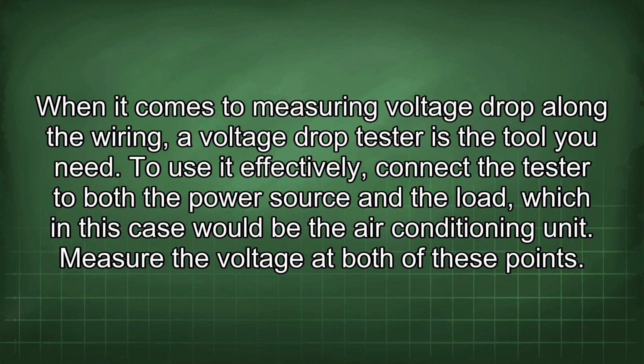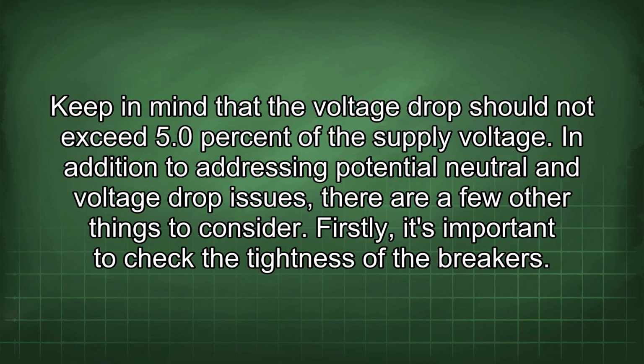When it comes to measuring voltage drop along the wiring, a voltage drop tester is the tool you need. To use it effectively, connect the tester to both the power source and the load, which in this case would be the air conditioning unit. Measure the voltage at both of these points. Keep in mind that the voltage drop should not exceed 5.0% of the supply voltage.